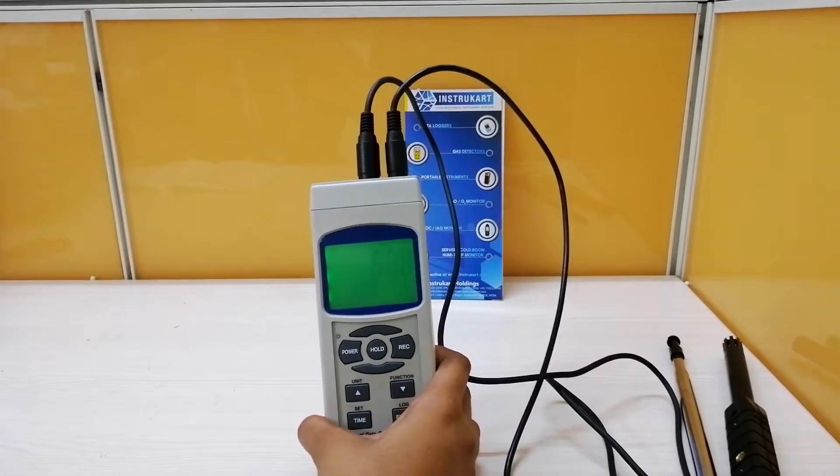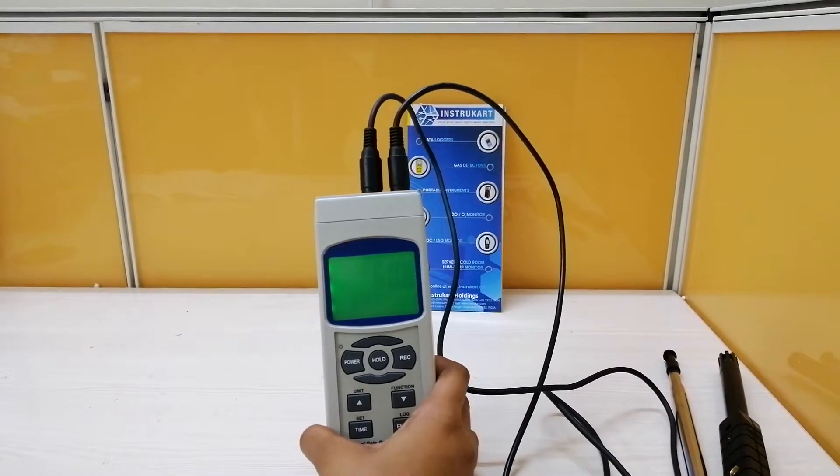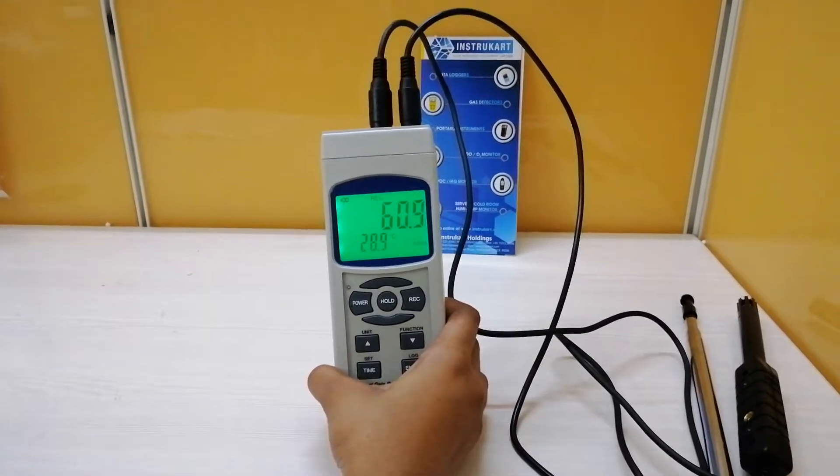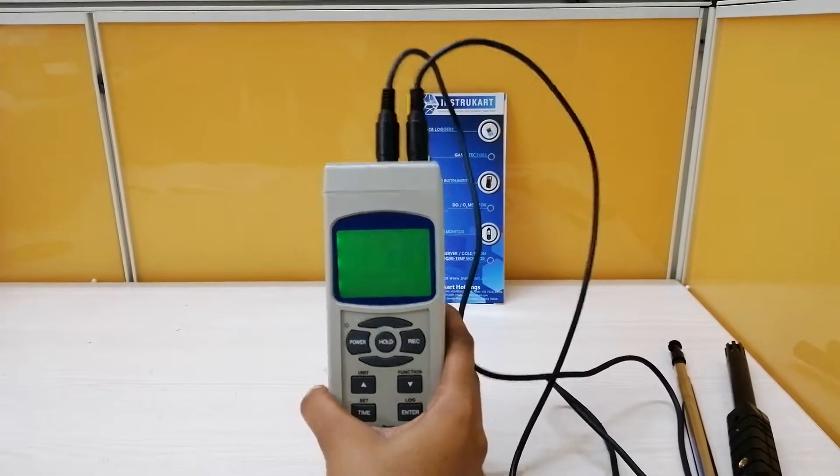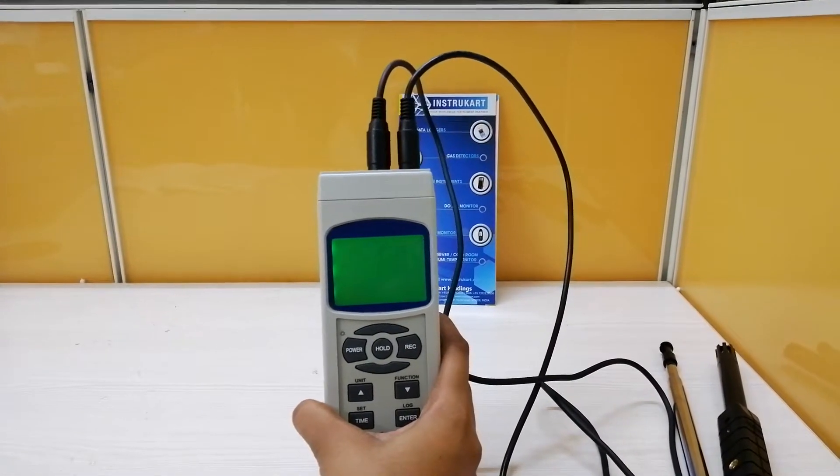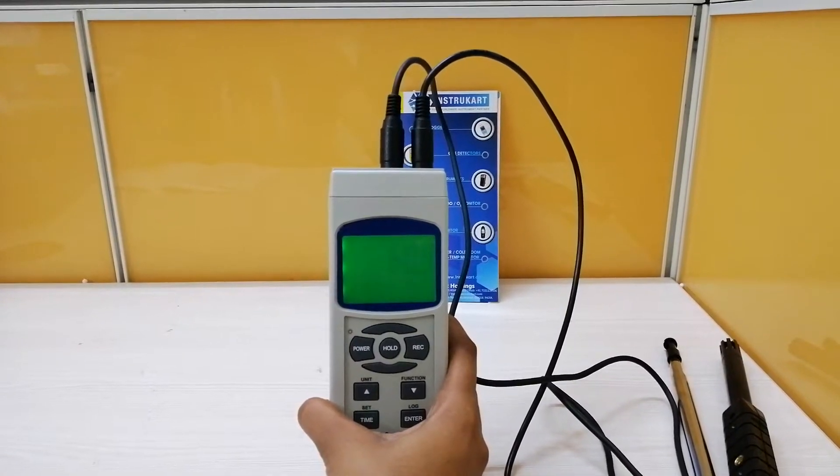This anemometer can measure the parameters like air velocity, air flow, air temperature, humidity, ambient temperature, dew point temperature, wet bulb temperature, and it has fast humidity measuring response time. It also has real-time SD card memory data logging.